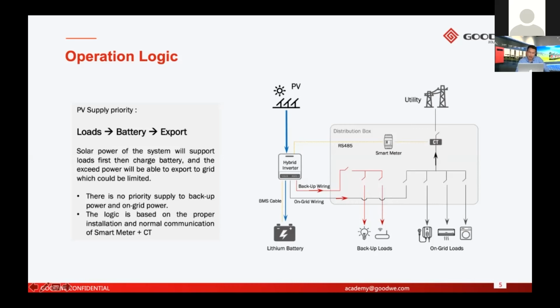For hybrid systems, like I said, if the PV power is enough, they will support the load first. Here they have two loads. One is the backup load, an off-grid supply load. The other is the on-grid load, connected on the grid side. These two loads have no priority, so they are supported together. The system calculates the total power of the loads, not how much is backup and how much is on-grid. It takes all the load consumption together as one.